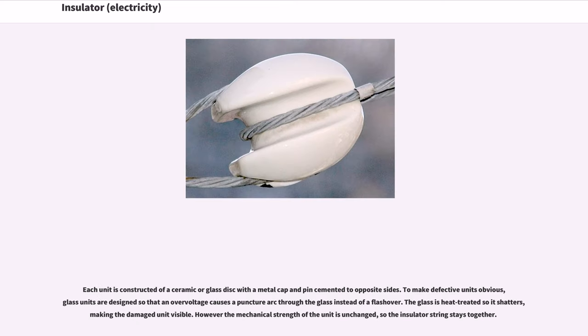Each unit is constructed of a ceramic or glass disc with a metal cap and pin cemented to opposite sides. To make defective units obvious, glass units are designed so that an overvoltage causes a puncture arc through the glass instead of a flashover. The glass is heat-treated so it shatters, making the damaged unit visible. However, the mechanical strength of the unit is unchanged, so the insulator string stays together.